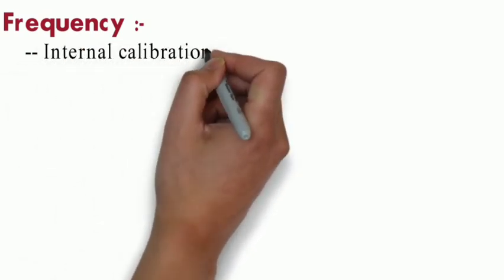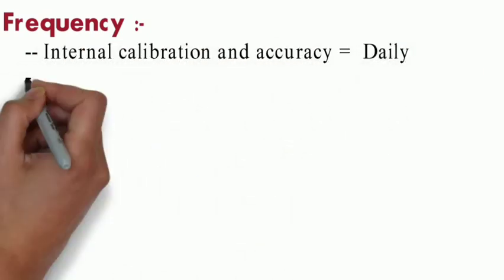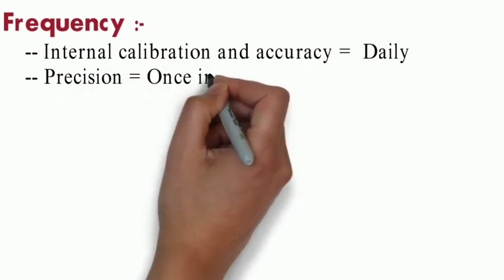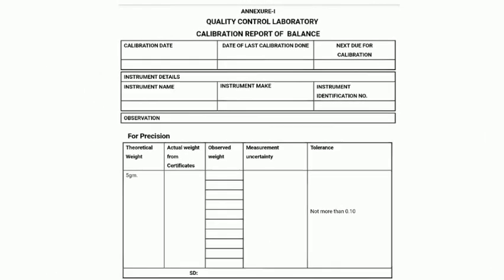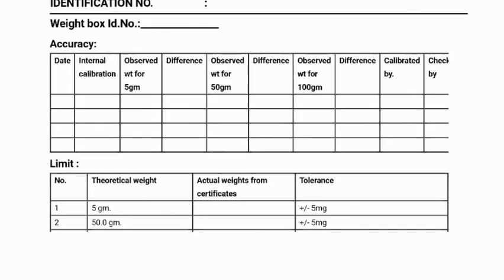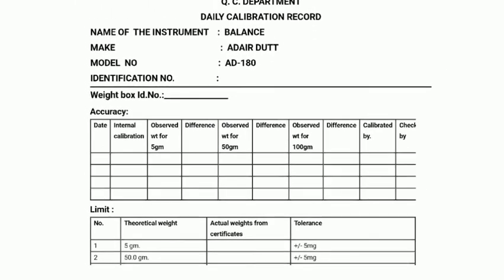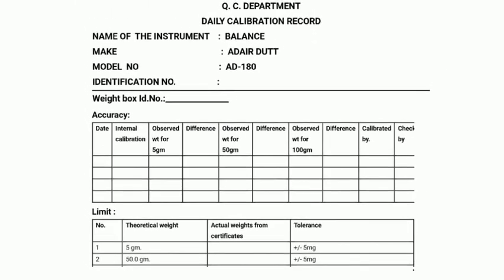Frequency: internal calibration and accuracy we have to check daily, precision once in a month. This is the Annexure 1 we discussed. We have to fill this annexure and Annexure 2, then submit. Responsibility to check is by executive and manager.